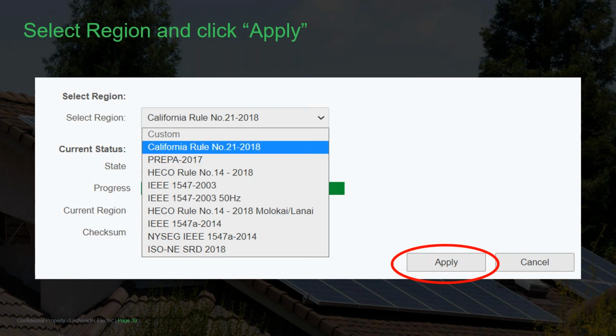Now turn off the DC breaker for the first XW Pro and energize the second XW Pro battery breaker. Repeat 120-volt firmware upgrade and region code selection for each unit. Once the third XW Pro is finished, it's time to program phase assignments.